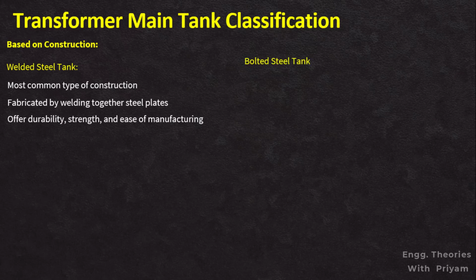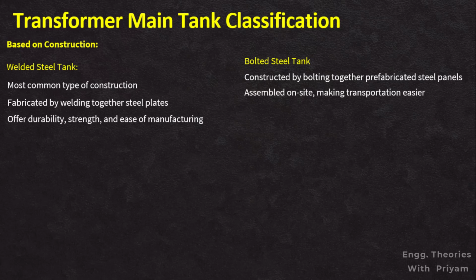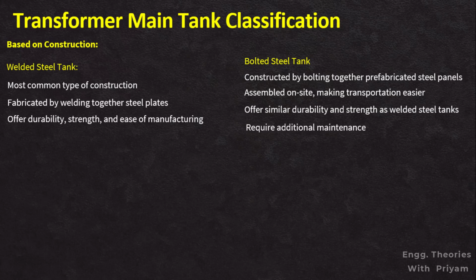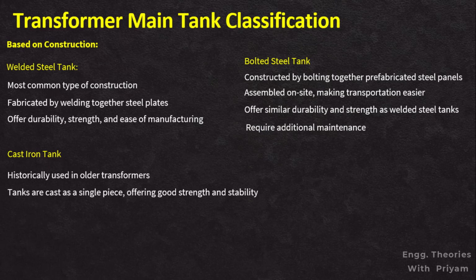Bolted steel tank. Bolted steel tanks are constructed by bolting together prefabricated steel panels. These tanks are assembled on site, making transportation easier for larger transformers. Bolted steel tanks offer similar durability and strength as welded steel tanks but may require additional maintenance due to the bolted connections. Cast iron tank. Cast iron tanks were historically used in old transformers but have been largely replaced by steel tanks. Cast iron tanks are cast as a single piece, offering good strength and stability. However, they are heavier and more expensive to manufacture compared to steel tanks.